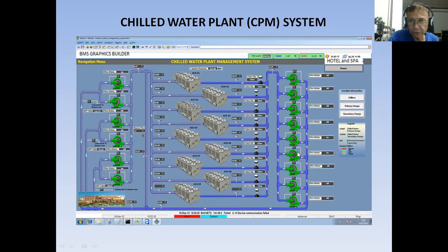It is also a good idea to limit the monitoring points for a whole graphic so that the loading and polling of the online data will be fast. Here for my primary pumps, I'm just monitoring the run status.